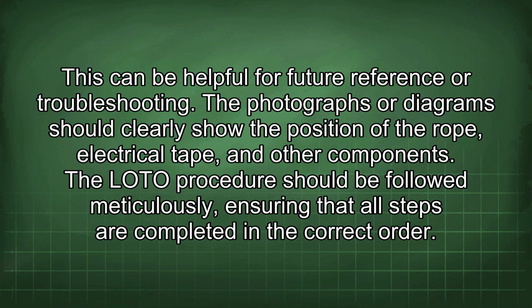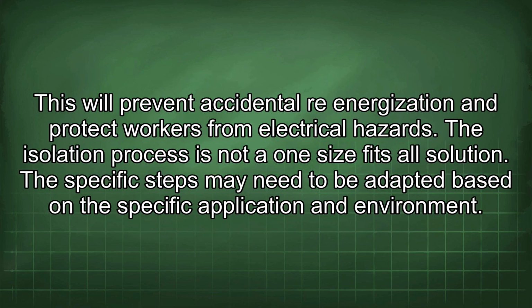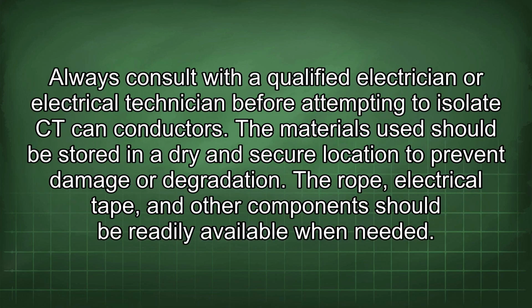The photographs or diagrams should clearly show the position of the rope, electrical tape, and other components. The LOTO procedure should be followed meticulously, ensuring that all steps are completed in the correct order. This will prevent accidental re-energization and protect workers from electrical hazards. The isolation process is not a one-size-fits-all solution. The specific steps may need to be adapted based on the specific application and environment. Always consult with a qualified electrician or electrical technician before attempting to isolate CT conductors. The materials used should be stored in a dry and secure location to prevent damage or degradation. The rope, electrical tape, and other components should be readily available when needed.